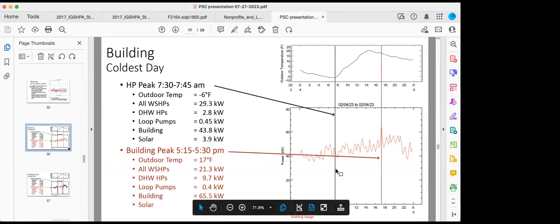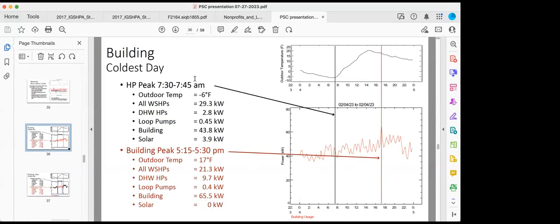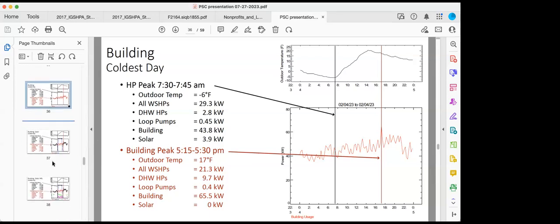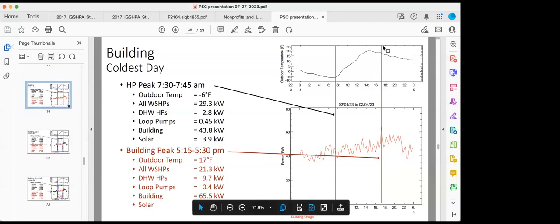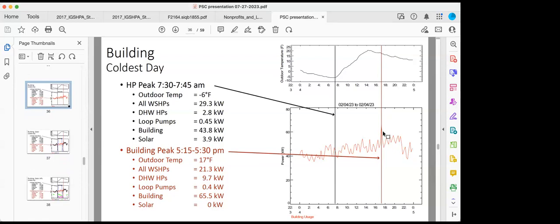So a few observations, emphasizing what I said before. This is the outdoor temperature on the peak day. The peak for the HVAC, for all the heat pumps, occurred again at 7:30 in the morning. However, the peak of the building occurred around 5 to 5:30 p.m., when it was much warmer, and it was no longer the heating system driving this. The point is we already have our peak in the system at that time, and that peak is much higher. In other words, once you've built a building like this, you don't have to upgrade the grid anymore. The grid is already correctly sized for that.